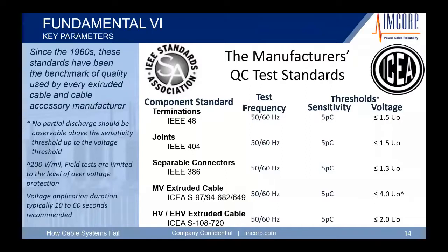So it's not a test that we recommend on new cables or aged cables, because on aged cables, if you do have some defects and they have been growing, these types of tests can actually make them grow more. So these are the tests that we adhere to. We do this in the field. These were only tests that could be done in a shielded room at the factory, and these, of course, pass all of these tests before they get to you.